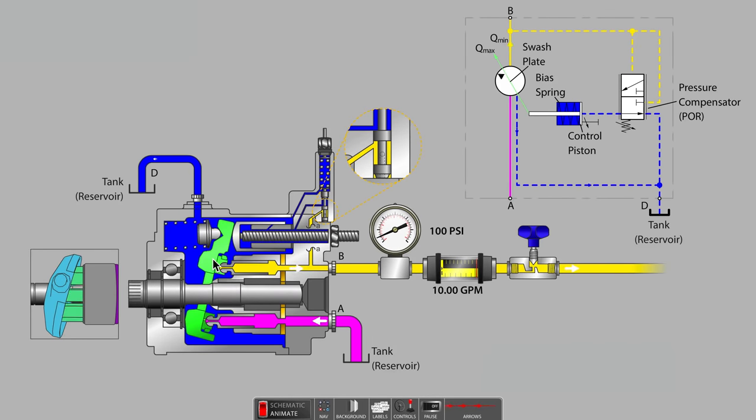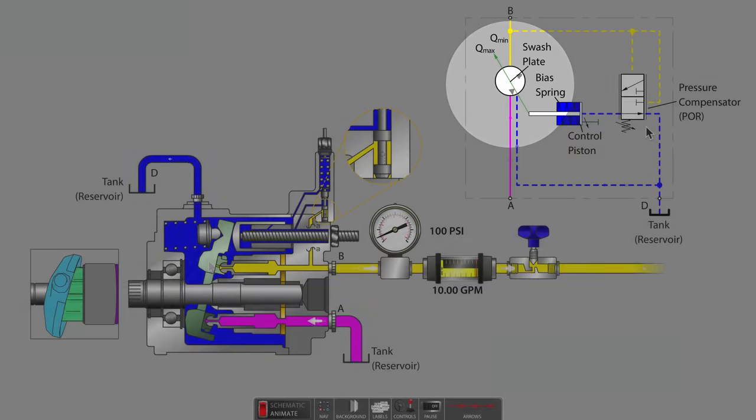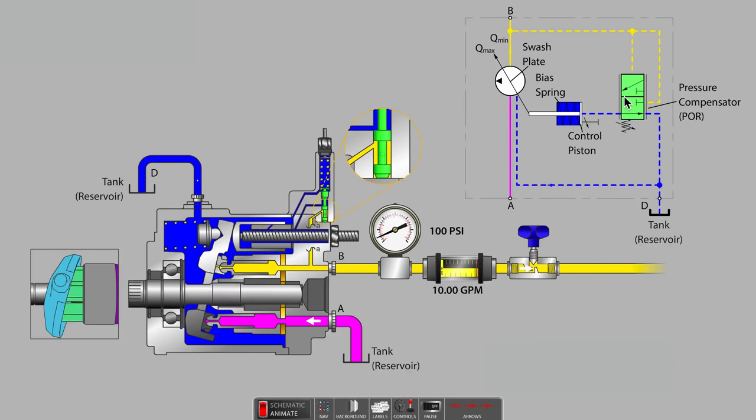When you see the green highlighting appear, don't forget to have a look at the matching symbol in the upper right-hand corner of the screen. Other typical names for pressure compensator are pressure override and pressure cutoff. All of these terms describe a feature that may allow us to go without a relief valve as is commonly found mounted to a T-fitting on the outlet line of a fixed displacement pump.